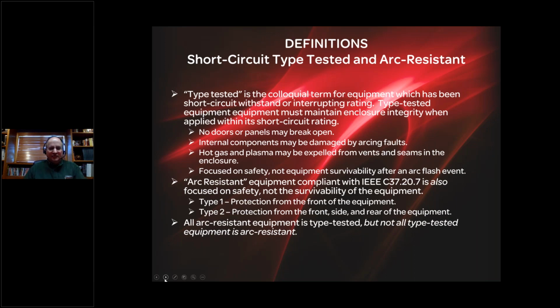So the focus here is on safety and not on equipment survivability, but we must have a short circuit type test in order to convert the equipment, with an arc quencher, to be arc resistant. Arc resistant equipment compliant with C37.20.7 is also, I want to be clear about this, focused on safety, not the survivability of the equipment itself. Type 1 protection under C37.20.7 protects you from the front of the equipment, and type 2 from the front, side, and rear of the equipment.